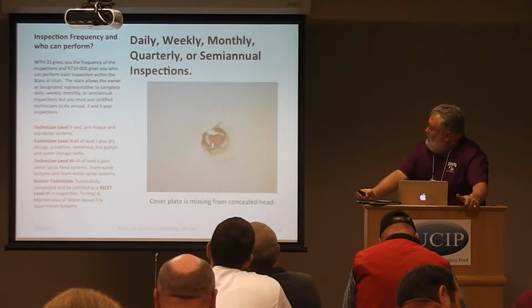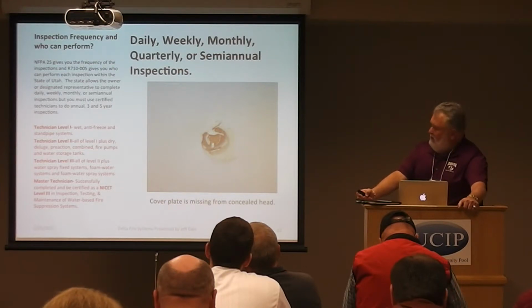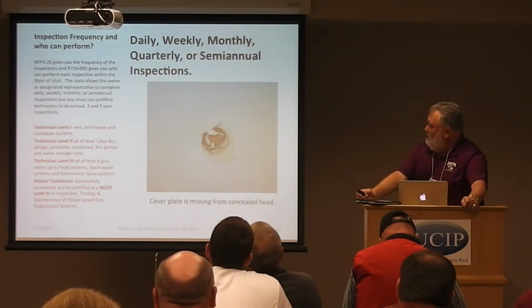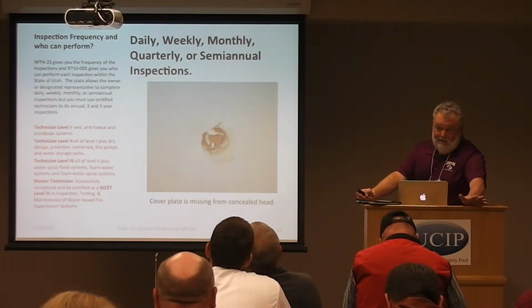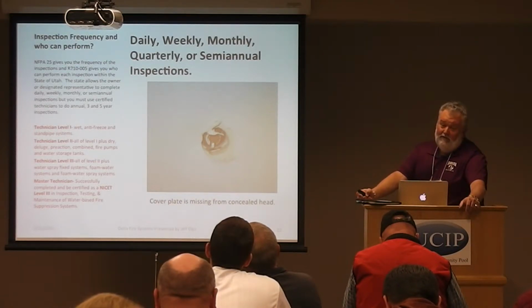Okay, like I mentioned before, NFPA 25 gives us the frequency of the inspections, and the R7105 tells us who can perform each inspection within the state of Utah. The state allows the owner or designated representative to complete daily, weekly, monthly, or semi-annual inspections. So you don't need to be certified in that. But in order to do an annual, 3, or 5 years, you must be certified. There's actually 4 different certifications within the state.